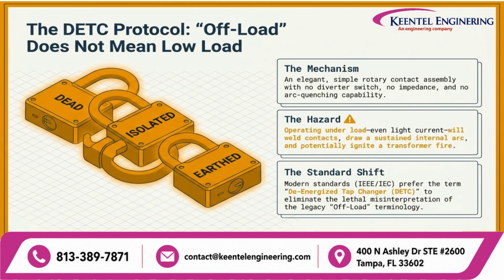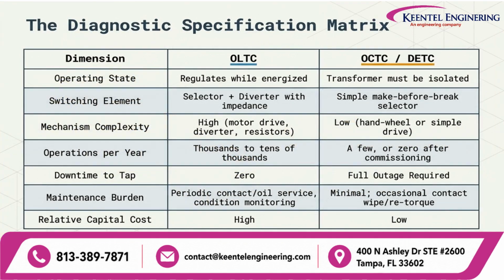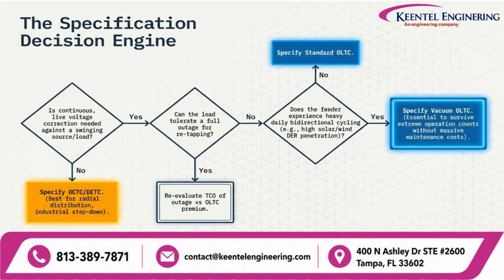One of the biggest misunderstandings in transformer engineering concerns off-circuit tap changers. The term off-load does not describe the electrical loading of the transformer. Instead, it means the transformer must be completely de-energized before changing tap positions. Even if the transformer is carrying zero customer load, changing taps while energized can create dangerous electrical arcs, equipment damage, and serious safety hazards. Therefore, DETCs require a complete isolation procedure before operation. Understanding this distinction is essential for safe transformer maintenance and proper operational planning. The appropriate choice depends on system operating philosophy, rather than simply equipment cost. Choosing the correct tap changer follows a structured engineering decision process.